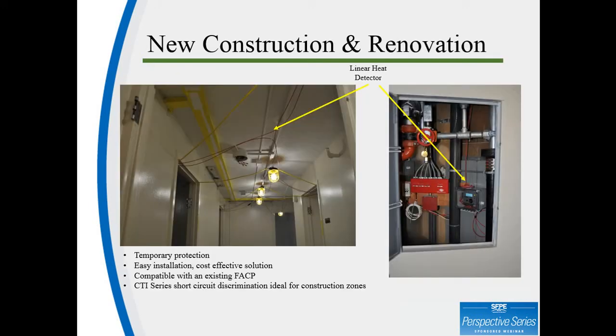Earlier, I mentioned two new applications where we are seeing a lot of activity. New construction and renovation is one of these applications. We've seen a recent increase in the use of linear heat detection, specifically our CTI series, as temporary detection while a building is being renovated. Typically, many of the spot detectors are removed during the renovation process, but the building fire alarm control panel remains active. Our interface module is connected to the building control panel, and then the linear heat detector is laced throughout the facility. This enables 24-hour fire detection in a facility where some or all of the permanent system has been temporarily taken offline.